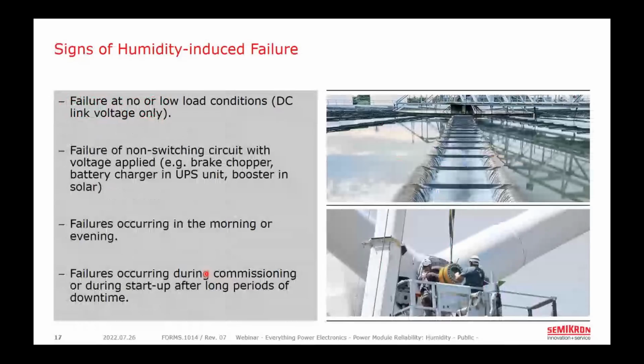So to that end, I just want to briefly list some things to consider if you do have some seemingly unexplained failures of systems, particularly under the following conditions. Since the failures we just described are voltage breakdown failures, that means that you don't necessarily need to be processing current to have such a failure. The chip only needs to be in a blocking state with voltage applied across it. As we'll see, there are periods of time such as the early morning or evening for outdoor inverters where conditions for this condensation are much more prevalent.